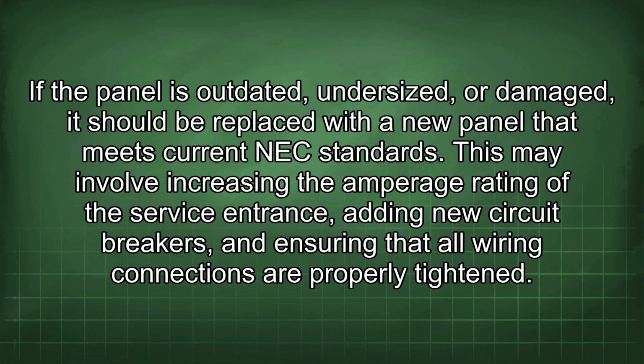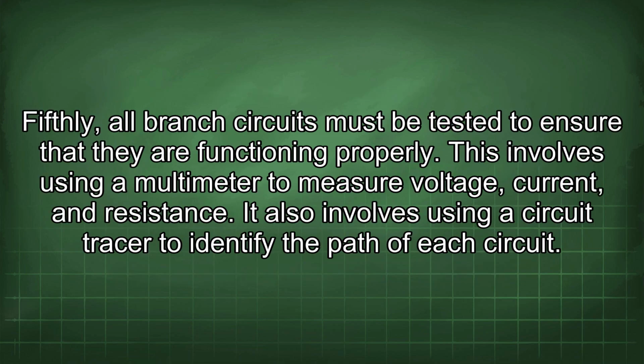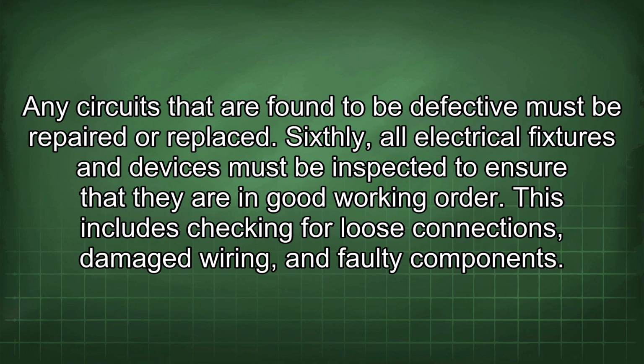This may involve increasing the amperage rating of the service entrance, adding new circuit breakers, and ensuring that all wiring connections are properly tightened. Fifthly, all branch circuits must be tested to ensure that they are functioning properly. This involves using a multimeter to measure voltage, current, and resistance. It also involves using a circuit tracer to identify the path of each circuit. Any circuits that are found to be defective must be repaired or replaced.